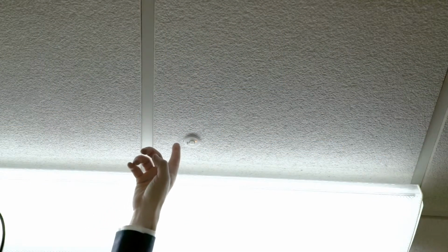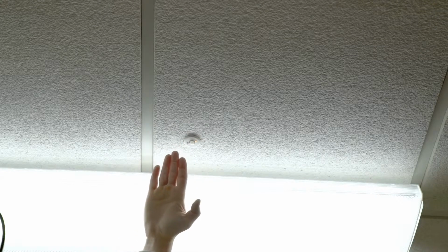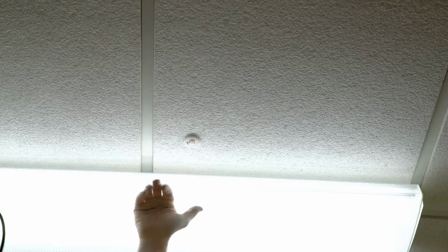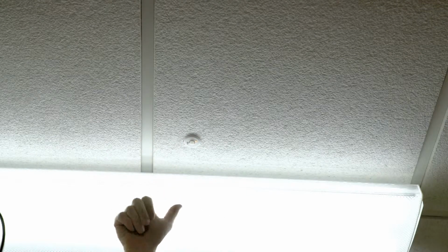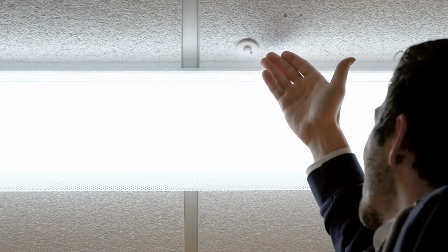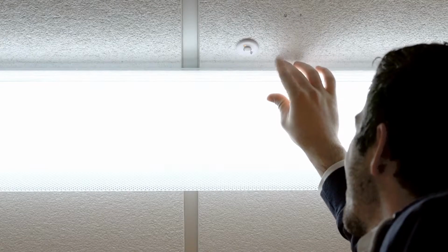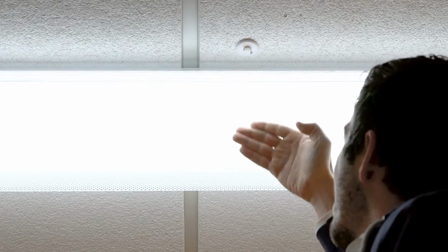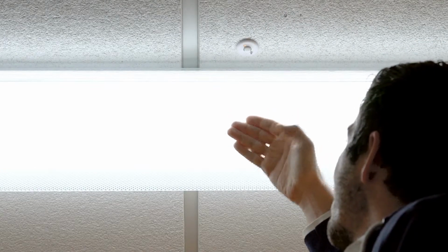Let's review a few sensor placement examples. Here's an example of a sensor that is well placed. It is located with clear, unobstructed view of the space around it. Here's an example of a sensor that could be placed better. As you can see, the sensor is placed too close to its fixture, preventing motion on the other side of the fixture from being observed.